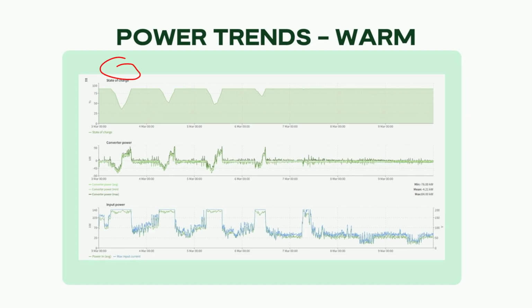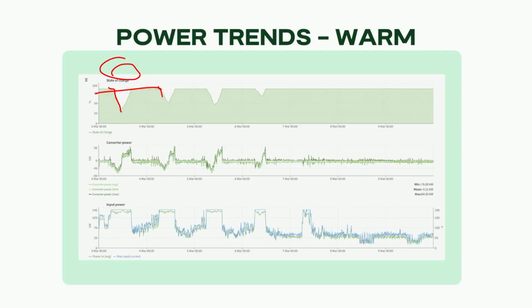you can see at the top here we have the state of charge, and we only start using the energy in the battery during times that the load overtakes or oversteps the 200 amp input current limit that we set in that case. So we don't use any energy from the battery while the load's under 200 amps. We only start using energy from the battery when the load overtakes that mark. And that's when you start seeing the battery discharge. However, when it was warm, there wasn't a huge amount of energy being consumed from the battery, which meant we only discharged a few times during the day.